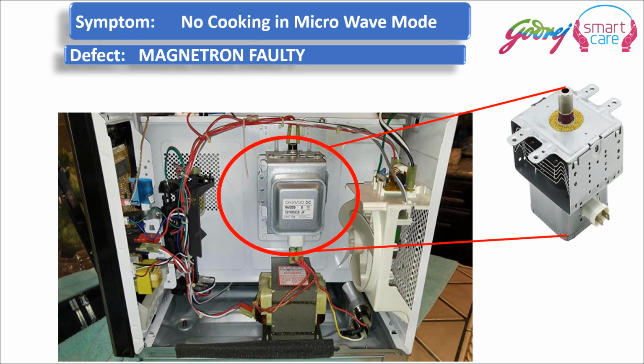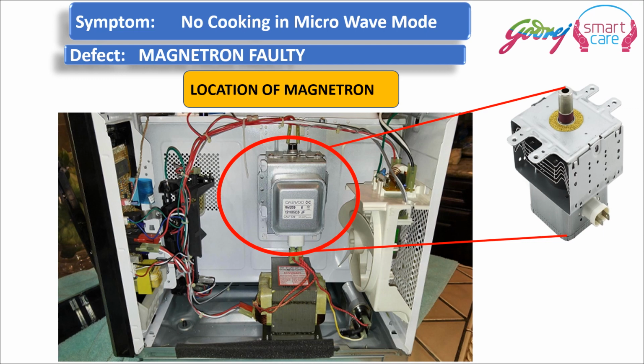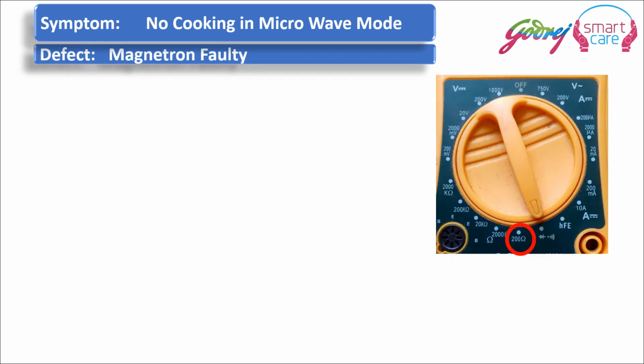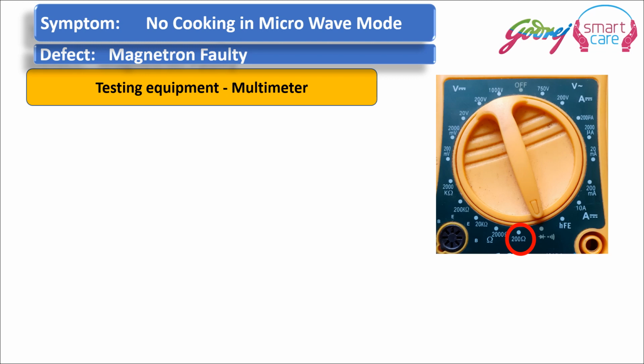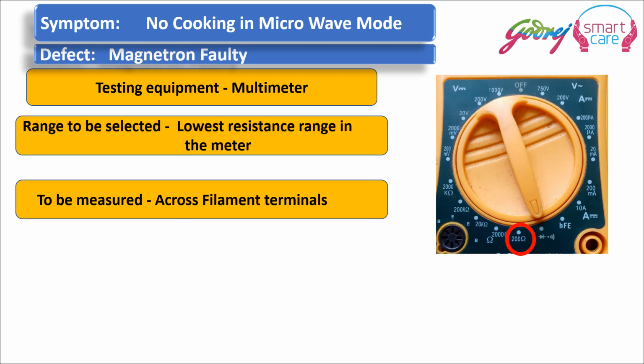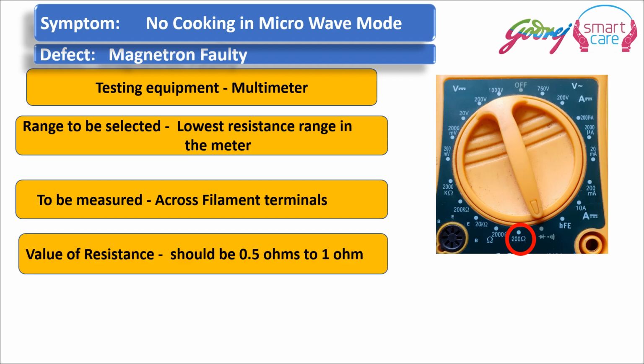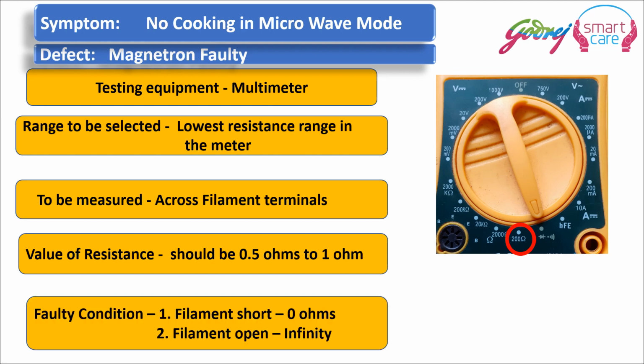Now to check whether the magnetron is faulty. This is the location of the magnetron. To check the magnetron which is faulty, we need a multimeter with the lowest resistance range in the meter. We have to set it in the lowest resistance range, and across the filament terminals of the magnetron, we have to check the resistance. It should be a very low value of resistance, between 0.5 to 1 ohms. A faulty condition is 0 ohms if the filaments are short inside, and if the filaments are open, then it will show infinity.